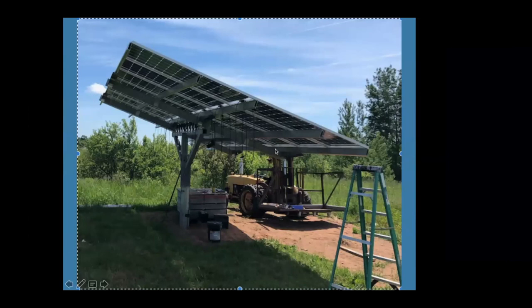Not all systems are installed on the roof. This one is ground-mounted with 16 solar panels. These are bifacial modules — a major new development that several manufacturers came out with a few years ago. Bifacial modules absorb sunlight from both the front and back of the module. The customer is trying to optimize energy from both sides, which is why he mounted all the micro inverters vertically to minimize shading. The jury is still out on how well bifacial actually works — personally, I don't think in most installations it's worth the extra legwork and cost.